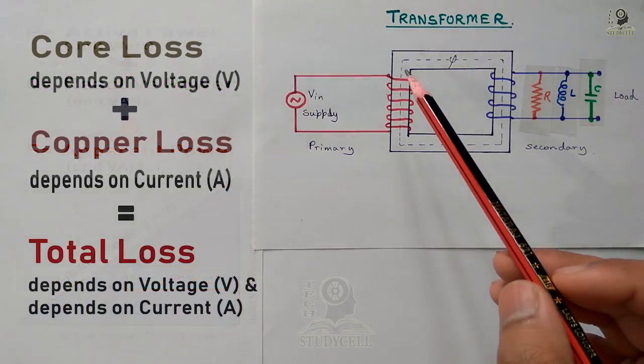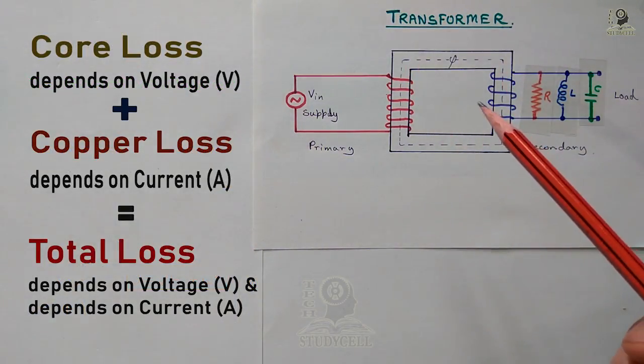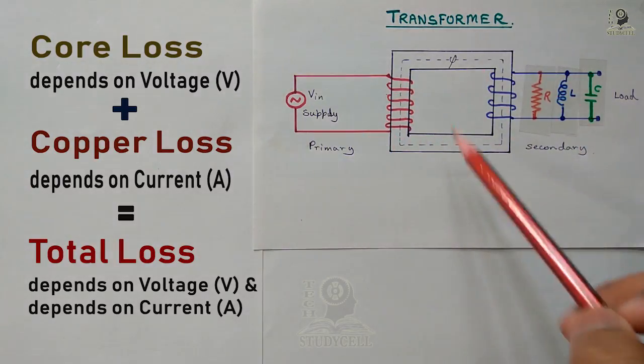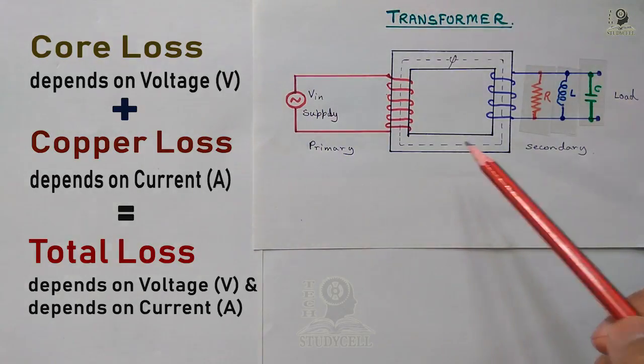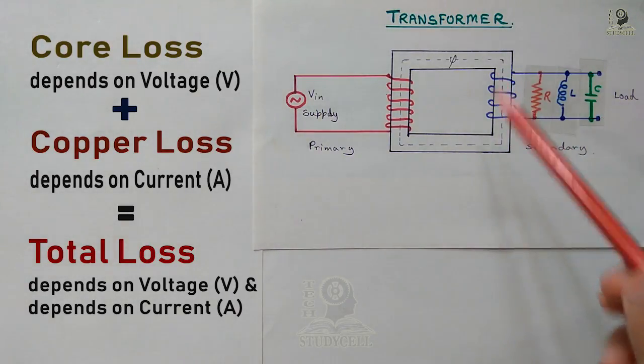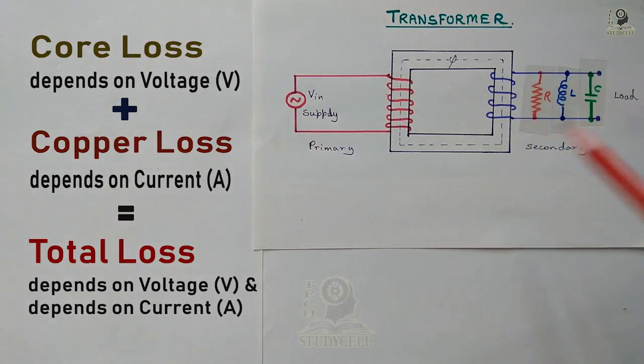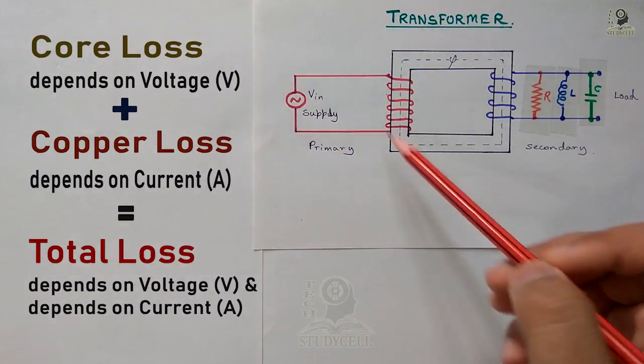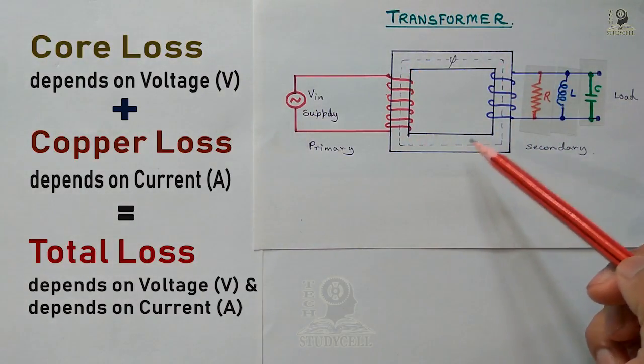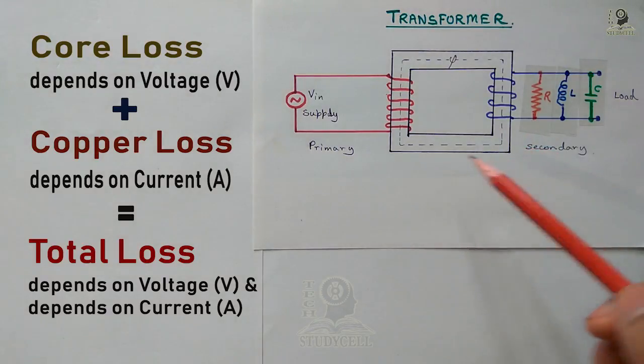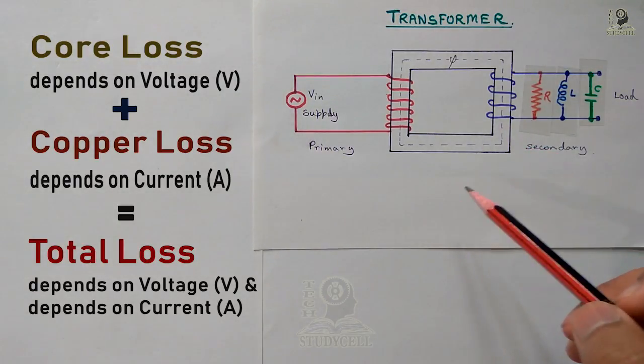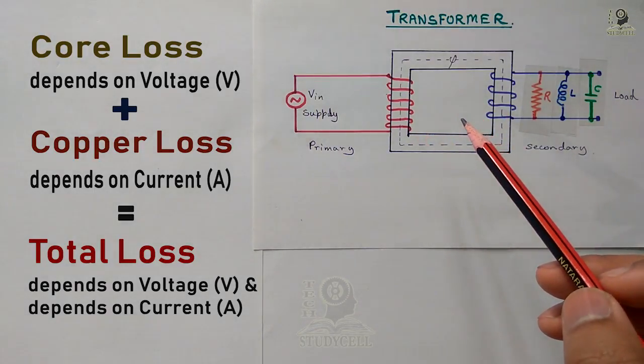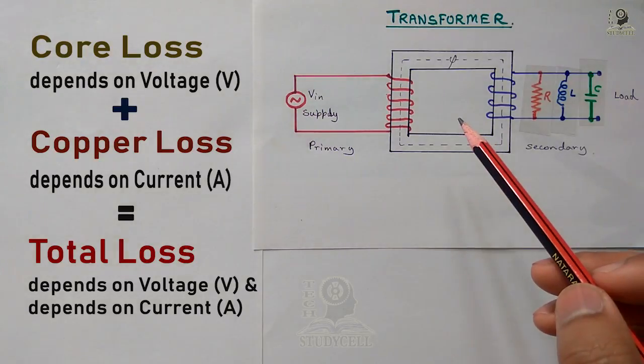The losses that occur in the transformer are core loss and copper loss. Core loss depends on the voltage, as the magnetic property of the transformer is constant. Copper loss depends on the current flowing through the winding, as the resistance of the winding is constant. From a loss perspective, we can also see that the losses depend on voltage and current. So we rate the transformer in VA — voltage ampere — and if the rating is higher, we use kilovolt ampere (kVA) or megavolt ampere (MVA).